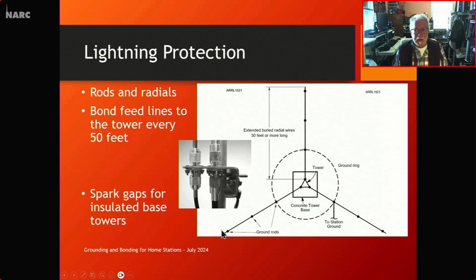You want to bond to the tower every 50 feet or so, because when you get hit by a lightning strike and there's a lot of current flowing in your tower, the inductance is enough to cause several kilovolts, sometimes tens of kilovolts, between the top and bottom of the tower. If your feed lines aren't bonded to the tower, they're at a wildly different voltage, and that's where you get damage to the cables.